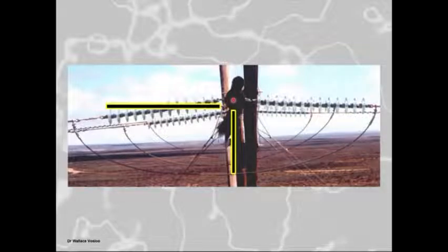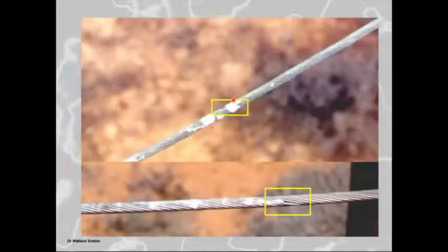Well, folks, what happened is that the poles delivered to site were not the correct length. The site supervisor never checked that they were the correct poles. They were installed, and two short poles were installed. Having installed two short poles, the actual window gap became smaller, and with the smaller window gap, we found that the jumpers could not be installed at their correct lengths and had to be shortened. And that is what caused the problem. The gap was mostly shortened in the center phase more than on the outer phases, because the window geometry was smaller due to the shorter poles that were delivered. So we now know that.